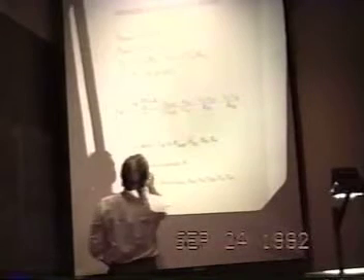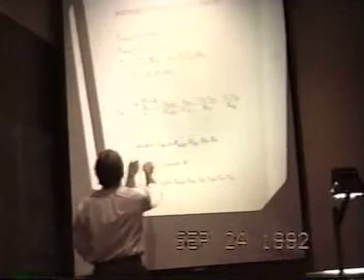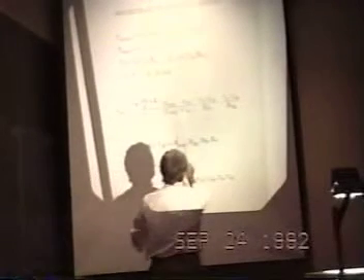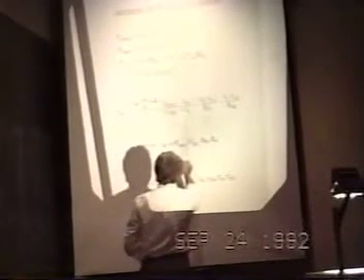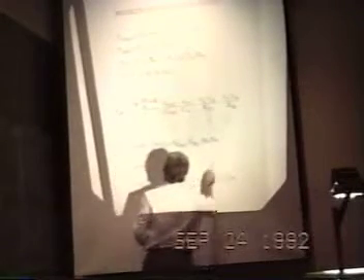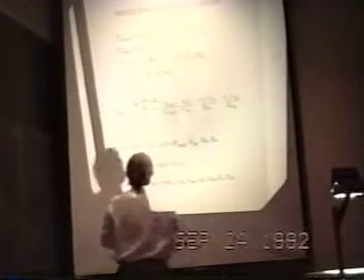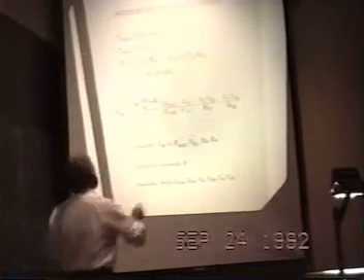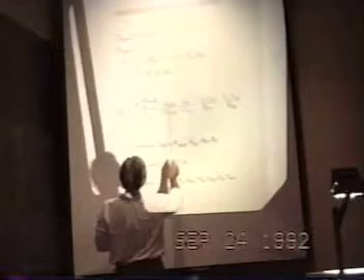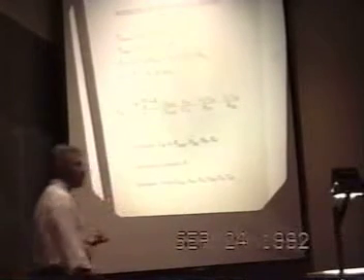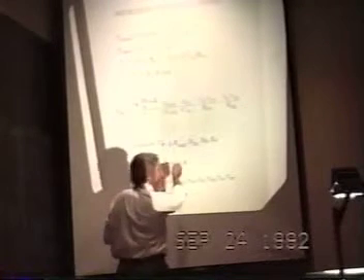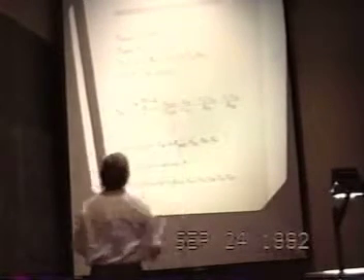this term due to the conductive transfer of heat out of the electrochemical environment, the resistance ratio of the inlet and outlet temperature sensors, minus the known sources of input power. This particular term in square brackets has useful properties. This resistance ratio difference has a wonderful effect in reducing susceptibility to systematic errors.